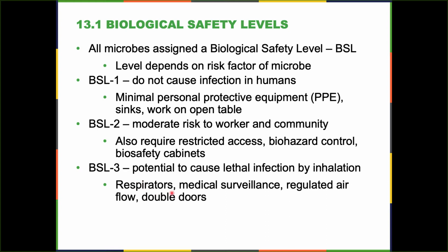So even outside of these double doors, to get into the facility, it's what we call negative pressure. When that door opens, all the air gets sucked from the outside to the inside. Because in the event that there's some sort of outbreak, some sort of spill, which is going to be very difficult given that it's through double doors and whatnot, right? In the event some crazy thing happens and the microbes may be able to get outside the lab, the negative airflow makes it such that all the air goes in, so none of the microbes will float out, right? So everything stays contained, and then you do the whole disinfection control prior to anyone leaving.